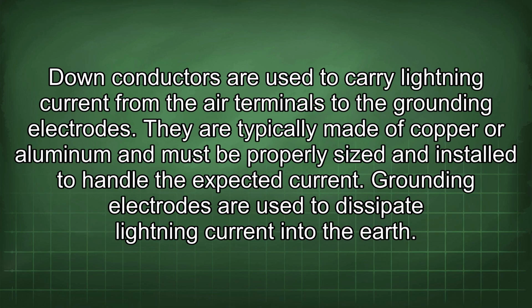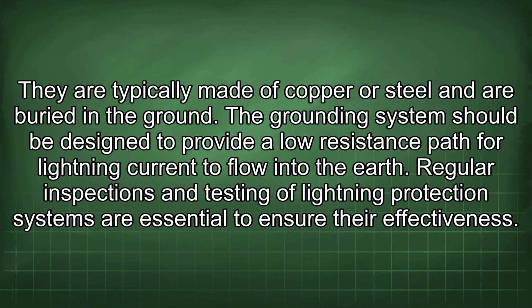Down conductors are used to carry lightning current from the air terminals to the grounding electrodes. They are typically made of copper or aluminum and must be properly sized and installed to handle the expected current. Grounding electrodes are used to dissipate lightning current into the earth. They are typically made of copper or steel and are buried in the ground. The grounding system should be designed to provide a low resistance path for lightning current to flow into the earth.